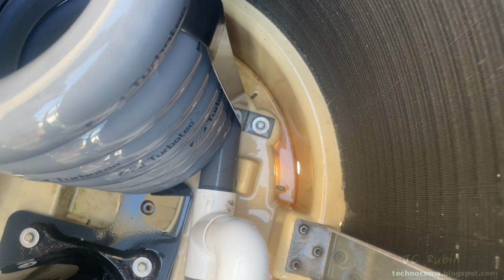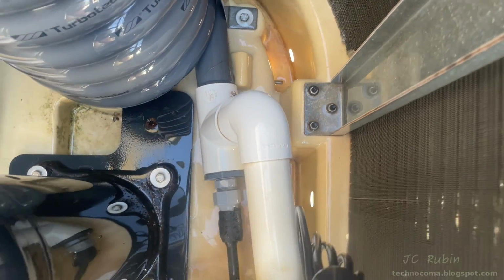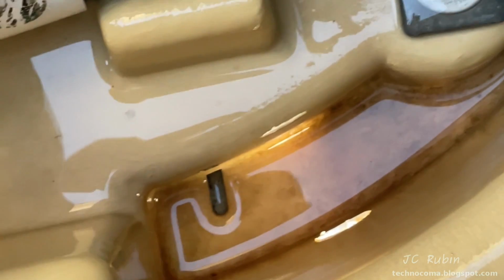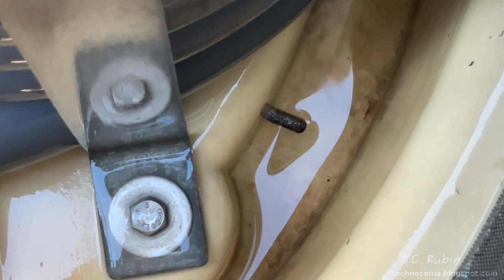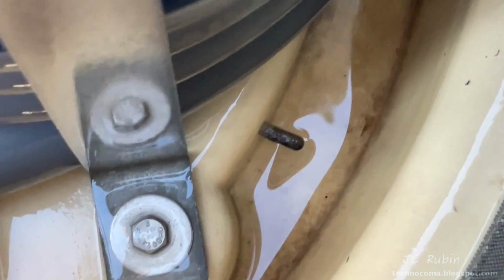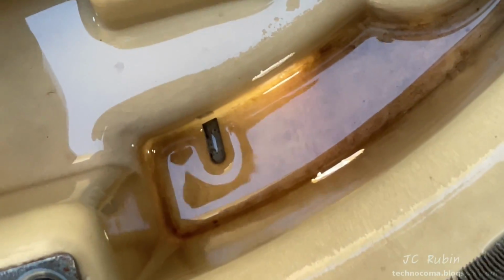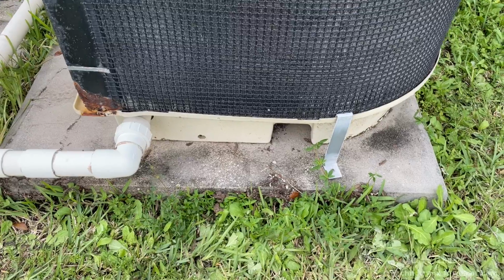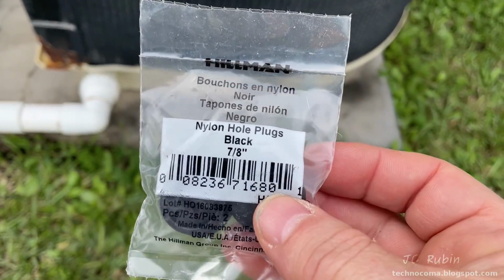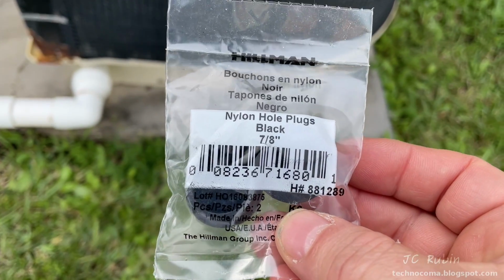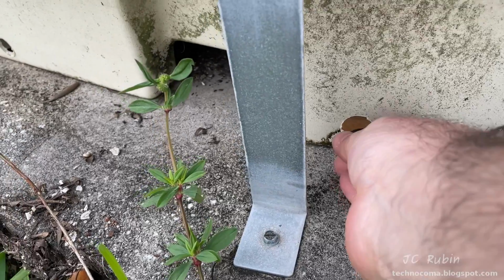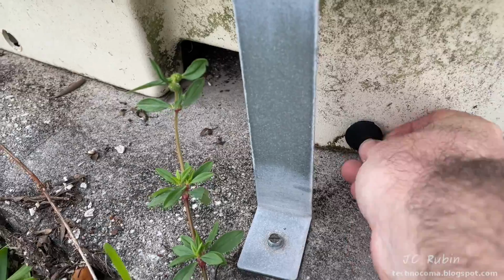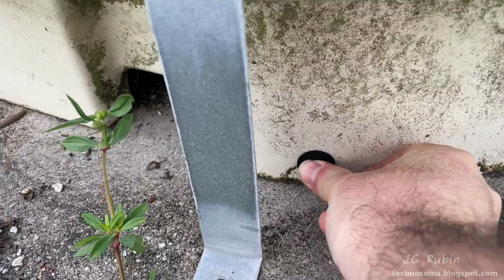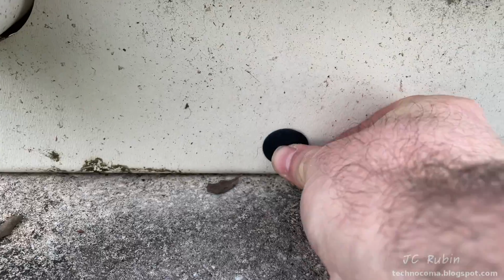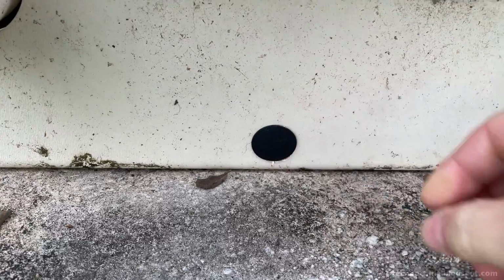With that, we could also see the drain holes around here and how incredibly small they are, which is why I couldn't see them, why they get stuffed so easily, and why it's impossible to clean this out once leaves fill up in here. 7/8 inch nylon plugs will be used to fill the holes because we don't want to keep them open, as it would lower the efficiency of this unit by drawing air from the bottom instead of through the coils. These can be taken off as needed to perform maintenance again.